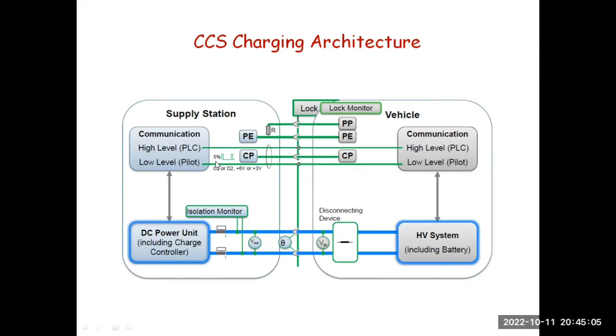Normally, the Type 2 charger has a 1 kilohertz signal, and the pulse width determines the current it can supply, starting from 10%. Here, when the pulse width is less than or equal to 5%, it means the communication is through digital, high-level communication—that is, power line communication. If it doesn't go below 5%, the high-level communication will not take place. So the low-level pilot initially has 100%, and once communication tries to start, it becomes 5%, indicating that high-level communication is going to take place.